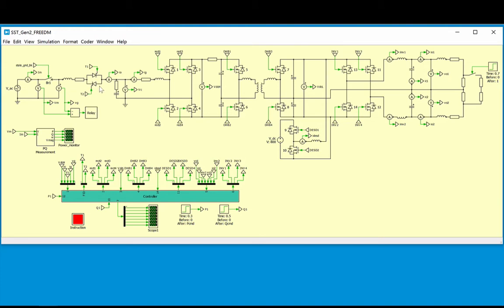The FID is comprised of two anti-parallel thyristors, whose purpose is to limit the inrush current. This can be achieved by controlling the firing angle of the devices at startup. A breaker is also included to physically disconnect the system from the grid in the event that a fault is detected.